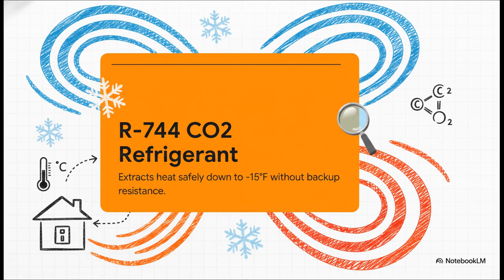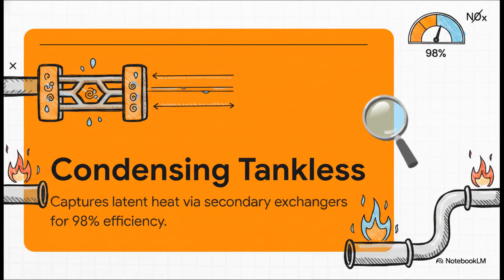But what makes this so incredible is the transcritical refrigeration cycle. Basically, it's a high-pressure system that lets these units safely rip thermal energy straight out of freezing air. No joke. They can work in environments down to negative 15 degrees Fahrenheit, producing perfectly hot 140-degree water, all without ever needing backup electric resistance elements. But hey, what if your home is sticking with gas? Well, the absolute pinnacle there is condensing tankless architecture.